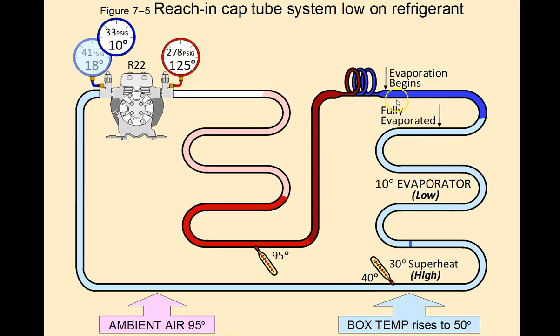Evaporation begins very early in the coil, it's fully evaporated, and then we start to pick up superheat. So we start at 10 degrees Fahrenheit, then we pick up more and more superheat until we get all the way down to where we're measuring at the outlet of the evaporator. We have a 10 degree evaporator temperature with a 40 degree line set temperature, giving us 30 degrees of superheat — which is super, super high.